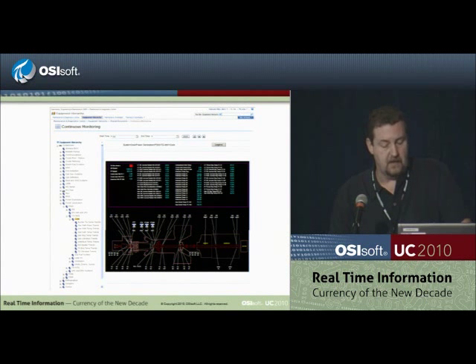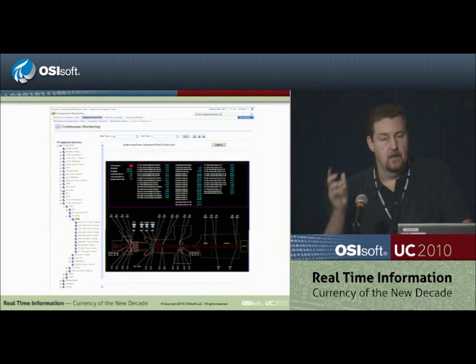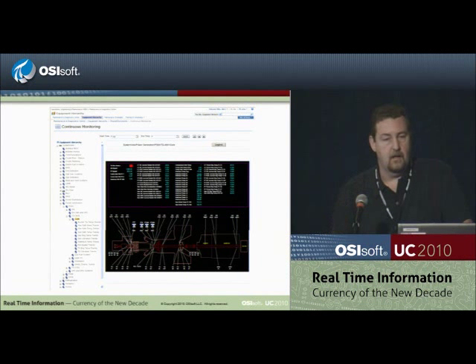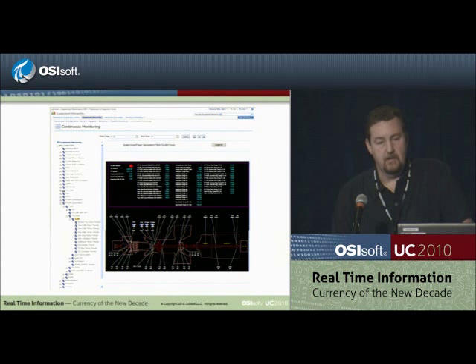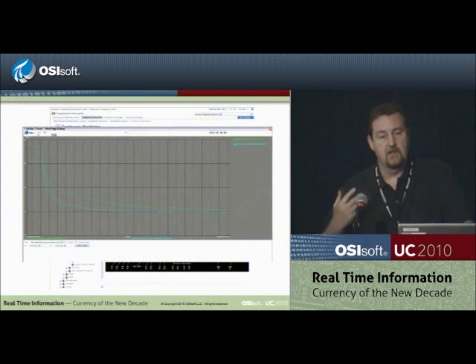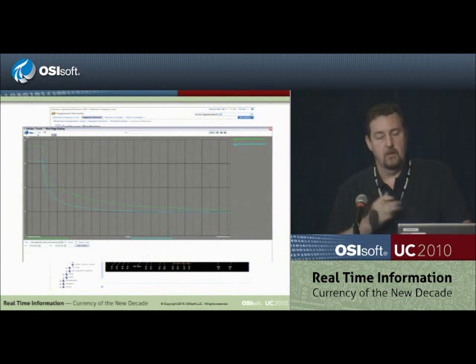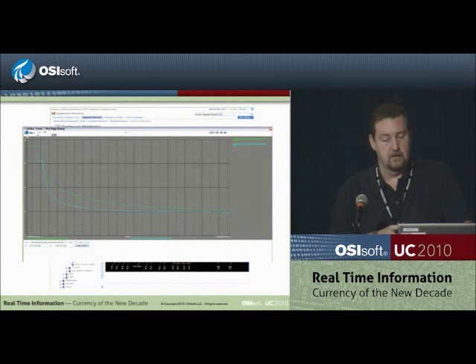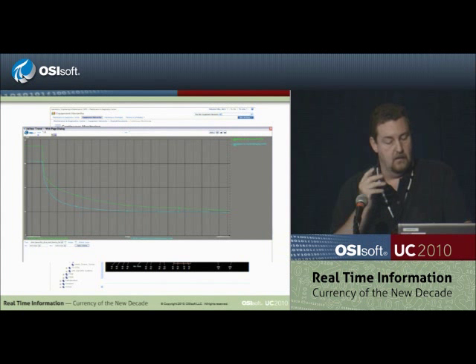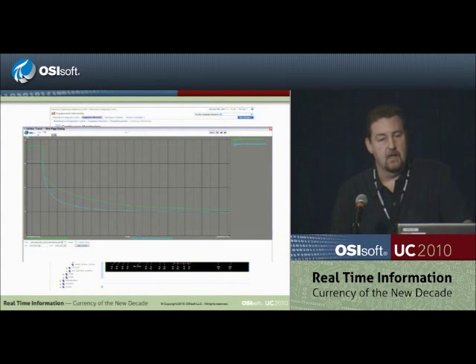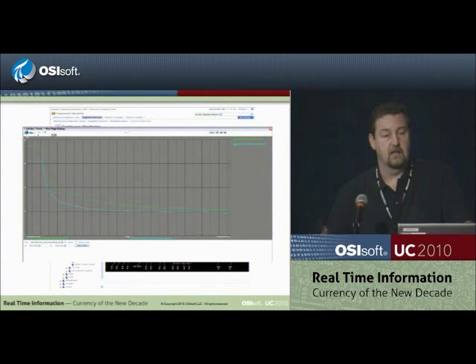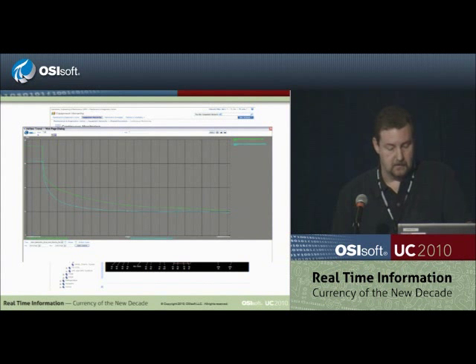All the analog values — this happens to be temperature — we can select any of them and do ad hoc trends on them. So if someone says, 'I'm looking at a transmitter on TG1 and I've got an exhaust temperature or bearing temperature that's not making any sense,' we're looking at the same drawing. We can grab it, do an ad hoc trend, and communicate that instantly to the team.